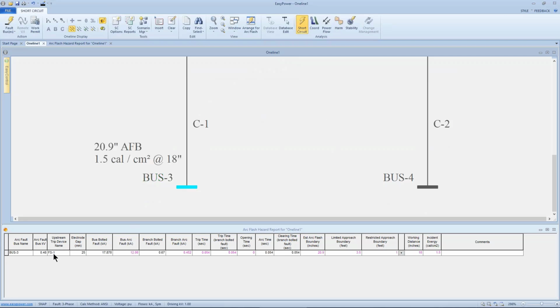It's still 480 volts. It's still the fuse as a protective device. It still has a 25 millimeter air gap. But now it only has 17,878, of which the IEEE model says the maximum current an arc will draw under these conditions is 12,060 amps. According to the data sheet for that fuse, the manufacturer says that fuse will clear the arc in 54 milliseconds. We put all those numbers into the IEEE equations. We get an incident energy of 1.5 calories and an arc flash boundary of 20.9 inches.